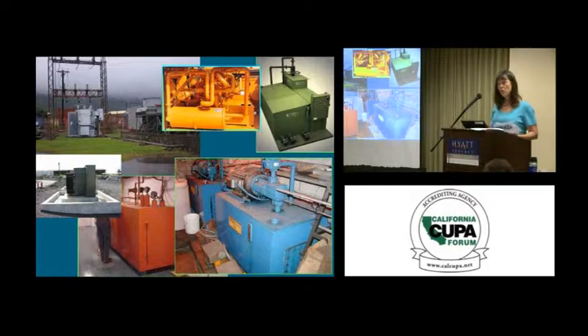So oil-filled operational equipment, and there's some photos here of the different types of equipment, so you'll see some examples. That would include an oil storage container or multiple containers in which the oil is present solely to support the function of the device or the apparatus. Some examples of that would be hydraulic systems, transformers, gearboxes, machining coolant systems, and other systems where the oil is solely in there to enable the operation of the device. So what was that acronym again? OFOE, oil-filled operational equipment. That type of equipment gets to have general containment. General containment applies for oil-filled operational equipment.